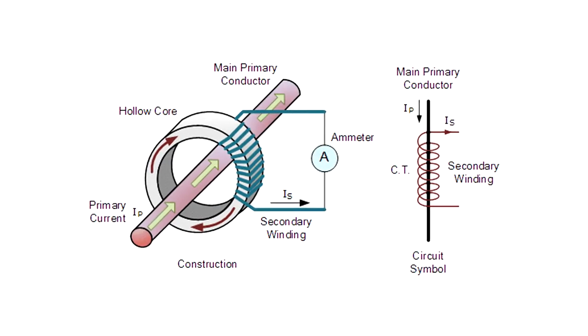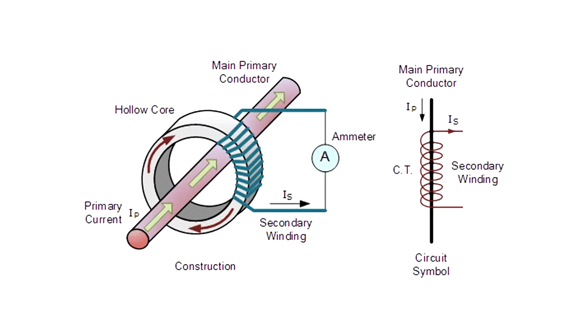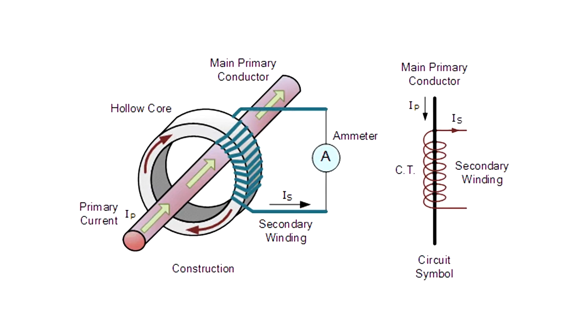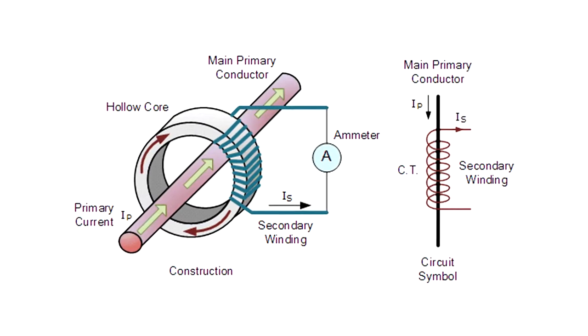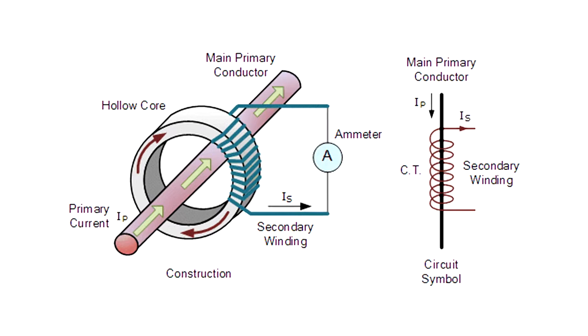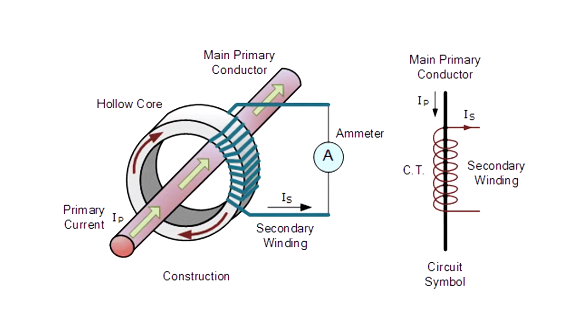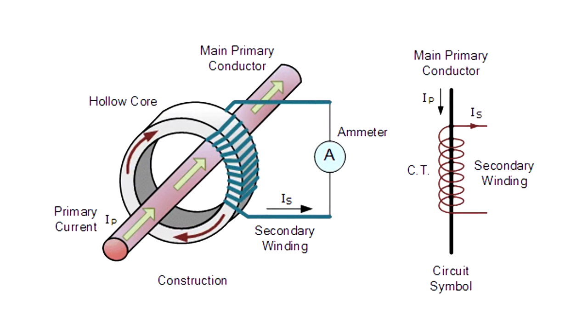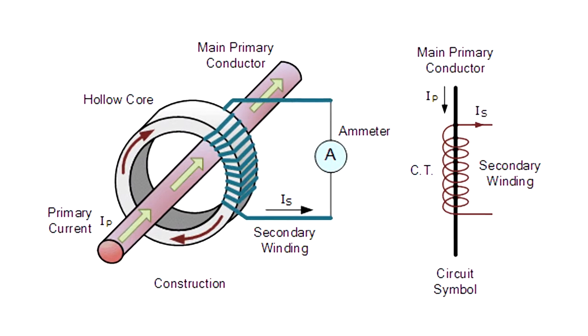The secondary winding is located inside the jaws of the current clamp. Due to a changing magnetic field from the alternating current on the primary side, a current is induced in the secondary winding, which is a current proportional to the primary current.